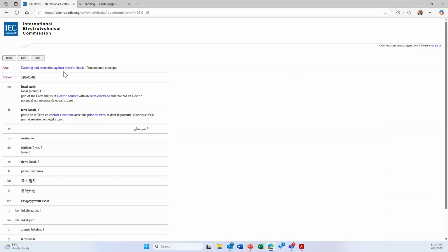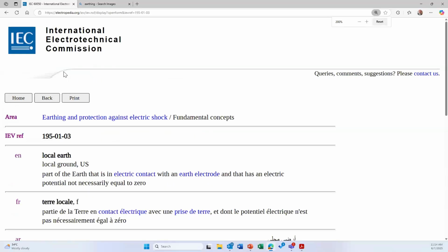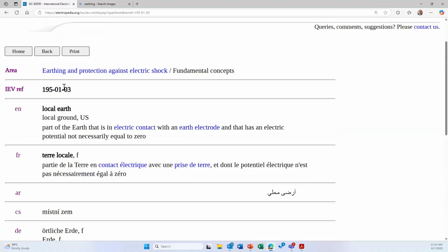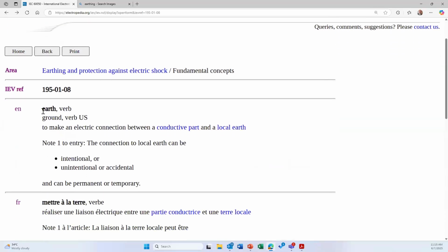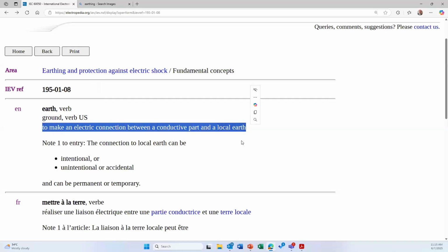What I am showing you is from the Electropedia. Electropedia is nothing but the electrotechnical vocabulary. So all the terms and definitions nowadays globally are becoming uniform. In order to make it uniform, the global agencies, ISO and IEC, have made the Electropedia, the electrotechnical vocabulary. So most of the standards are going or started using the global definition. Now, in the new definition of earth, you can see here, earth, verb, means it's not about the general mass of earth. It's a function. You can also see earth, verb, and ground, verb, US. In USA, the same name is not earth, it is ground. The meaning is to make an electric connection between a conductive part and a local earth.